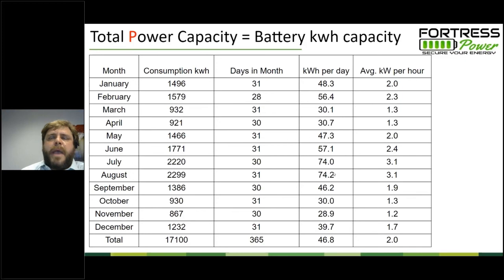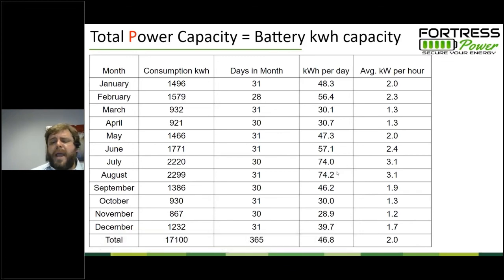For picking out the right battery capacity, it gets better with practice. But a lot of times, if you have, say, 12 months of electrical bills, it's not going to tell you a whole lot about how the building itself uses its power, but you still know what the end of the month consumption figures are. You can back that into average kilowatt hour use per day. Of course, sunny days versus cloudy days are going to differ, but it'll average out. And likewise, if you know how much energy you're using on average during the day, you also know how much energy you're using in a given hour.